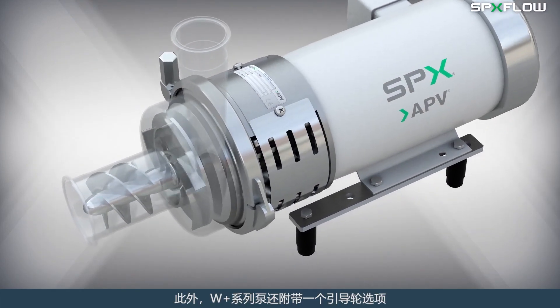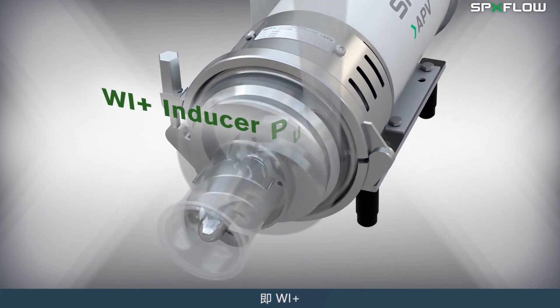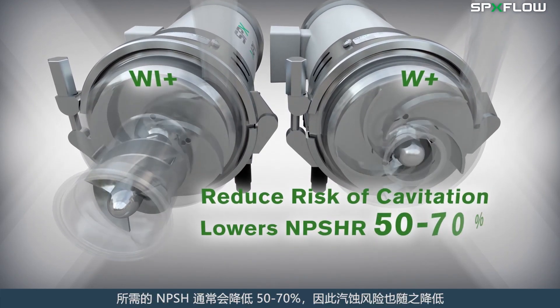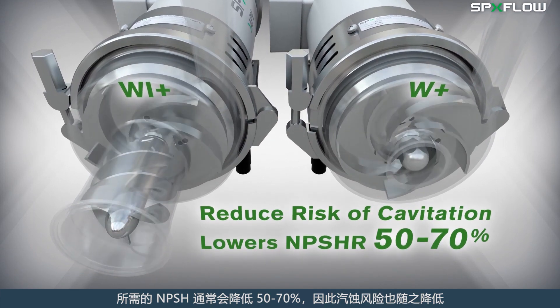The W+ pump also comes with an inducer option, which is a great alternative to changing the process design when NPSH availability is low. The inducer boosts the inlet pressure and the risk of cavitation is correspondingly reduced as the NPSH required typically drops by 50 to 70%.